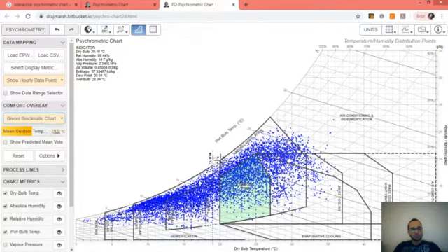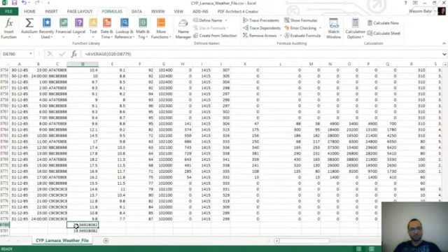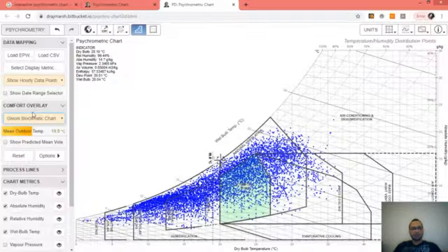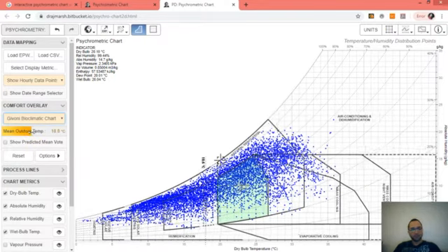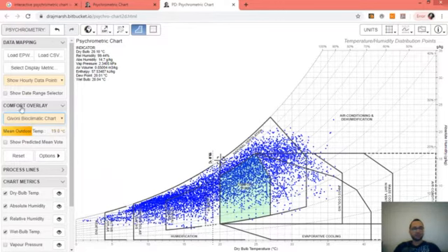The mean outdoor temperature by default is 19 degrees, which is the temperature that was identified earlier, so no need to change the value since it's the mean outdoor temperature for Larnaca. To remind you, I will reopen the Excel sheet file and show you that the mean temperature during 1 year, average yearly temperature is 19 degrees. Okay, so this value should be set to the correct value since it will change the chart allocation, and I will keep it.